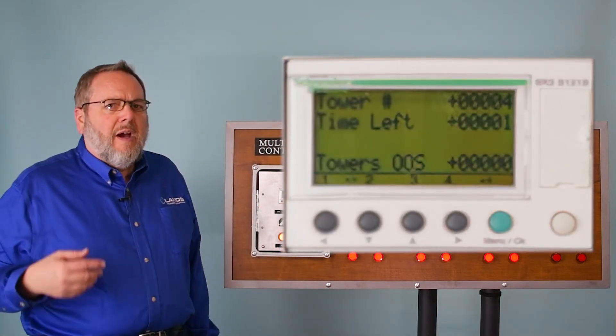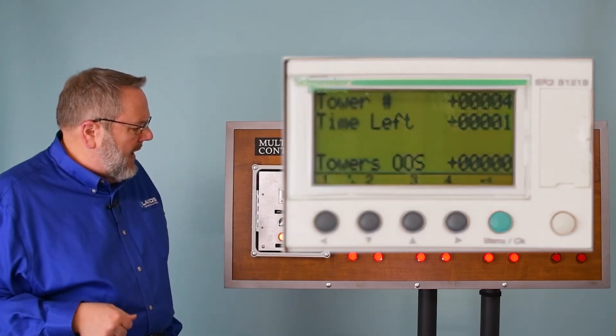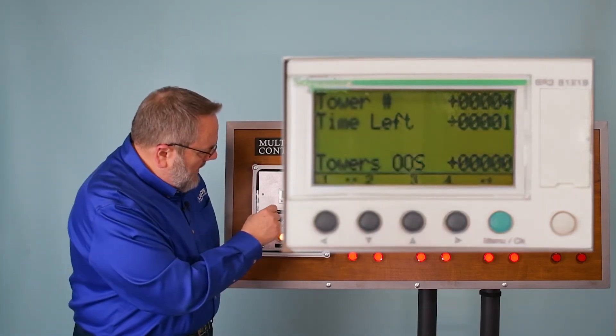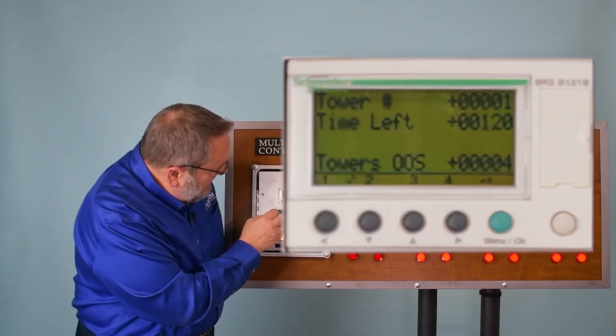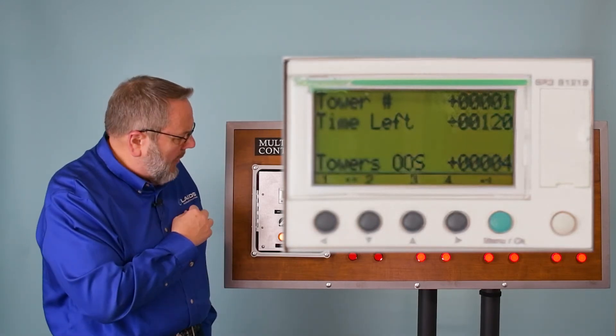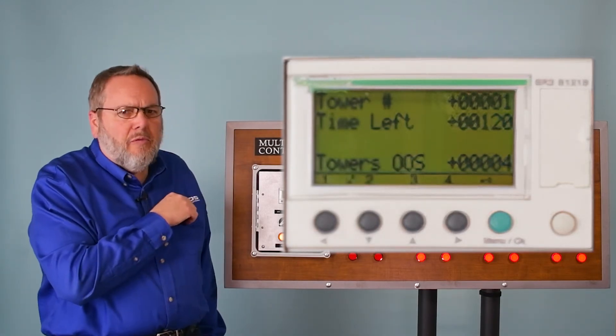And it should tell you when you get on here that you have on tower one that you have 120 minutes to run, and then that will start to count down. So if I go push this here, I'm going to bypass tower four. So you can see here now, it says on the display 120 minutes for tower one. So that's what it will run before it switches over.